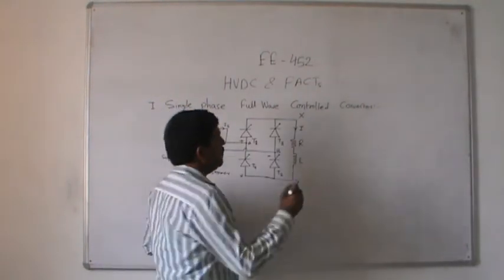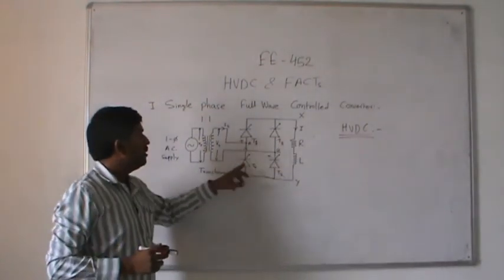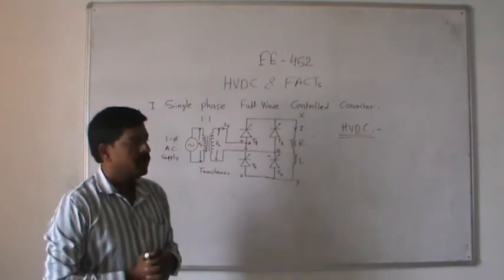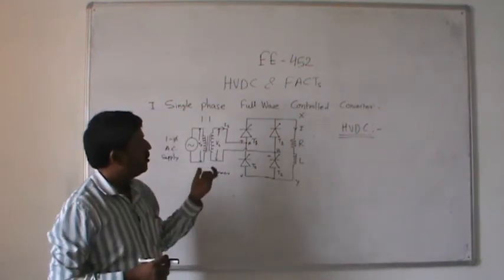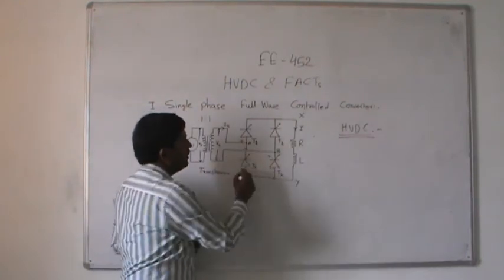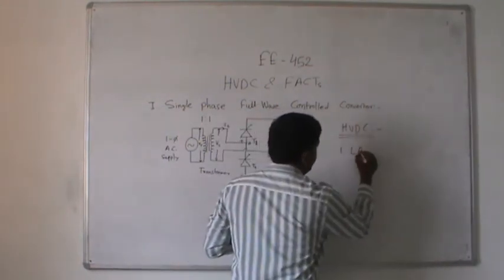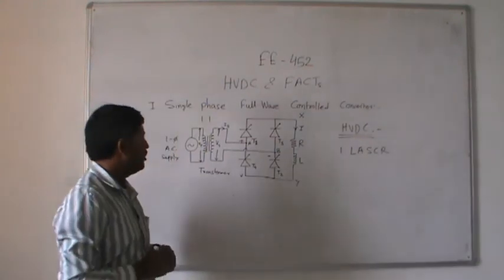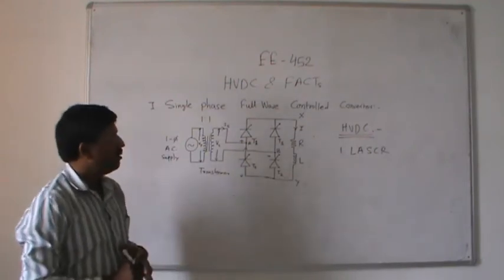In the case of HVDC, we use power semiconductor devices — specifically SCRs — for the switching purpose, because the typical voltage range and current rating of SCRs, as compared to other power semiconductor devices, is very high. Hence, for the conversion of AC to DC in HVDC systems, SCRs are preferred. There is also a special type of SCR called the LASCR — Light-Activated Silicon-Controlled Rectifier — which is used in HVDC applications.